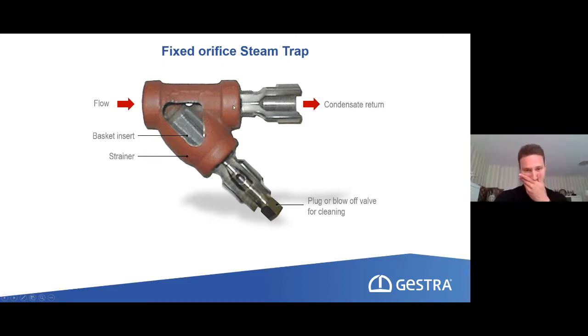So this is a design that doesn't have any control. Each and every other steam trap has a control function. They operate at different pressures and different temperatures with different amounts of steam and condensate. And this one is only for one fixed condition, but you never have that.